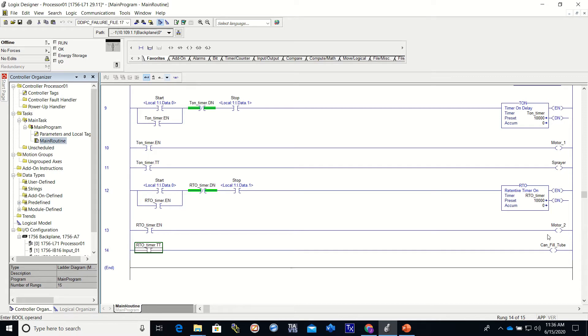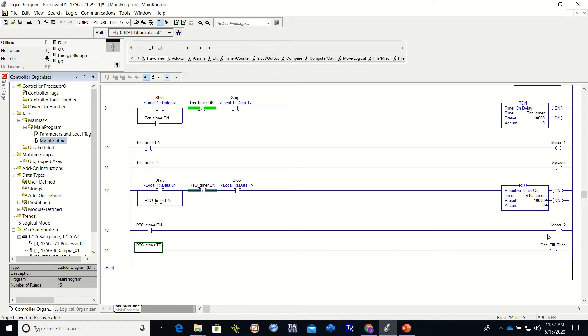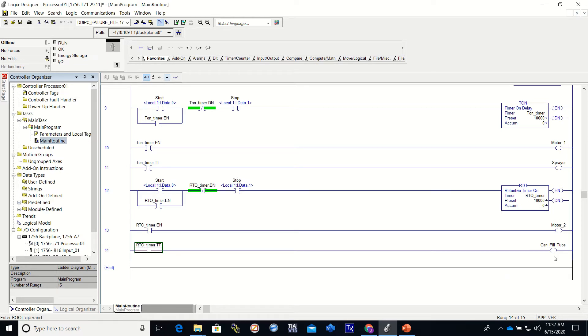So if you think about it, if we were trying to fill a can or a product and we lost the PLC and a normal timer, it would restart and it would start timing again and that would cause the product to overfill the can. With an RTO, we will not lose this time. So when our program starts back up, it will continue to fill the product and not overfill the can.